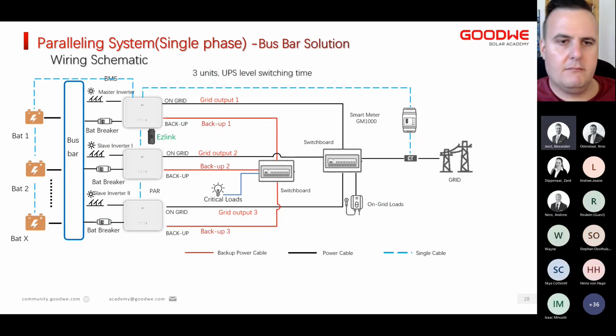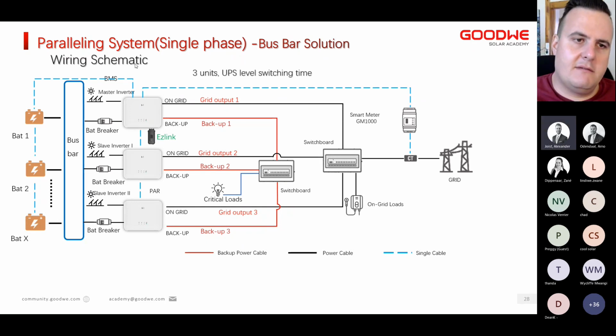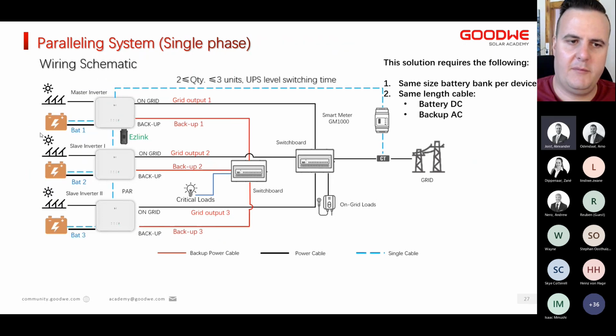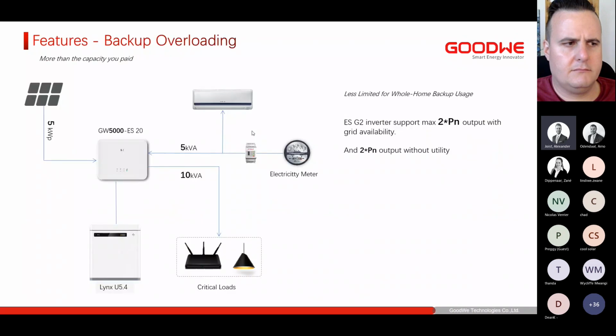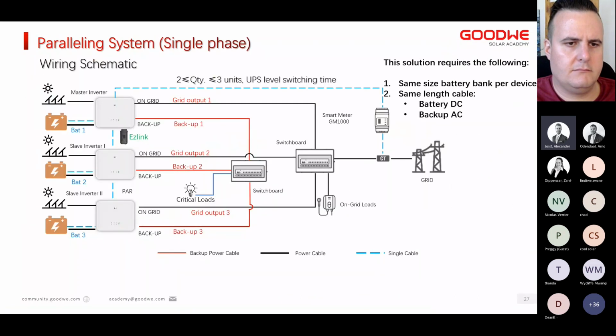Okay, and can I do the single phase paralleling with a common bus bar, or does each inverter have its own battery? Right, this primarily depends on the batteries, so whether the batteries can communicate with one another and then have a common point. Some batteries you might not be able to link and make one bank from. I know that BYD as well as Solar MD, that's what we carry, can do it. So I think that should be no problem.